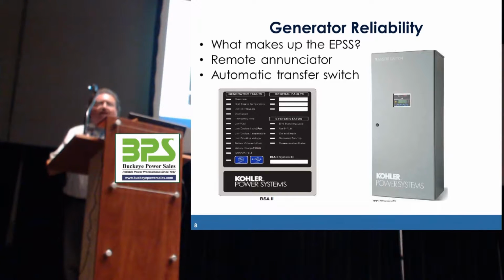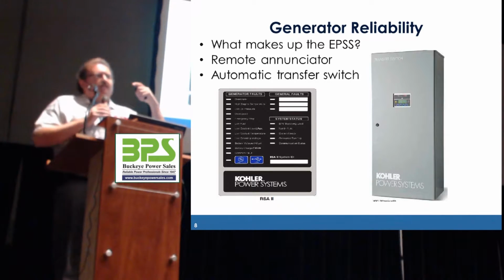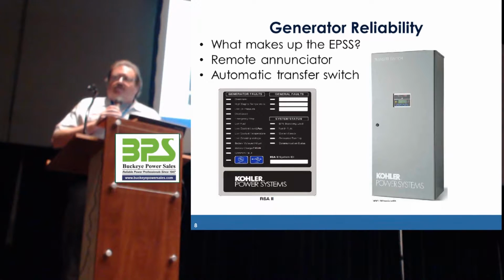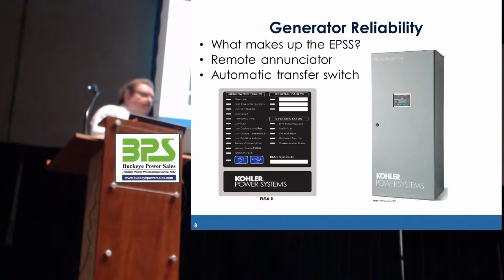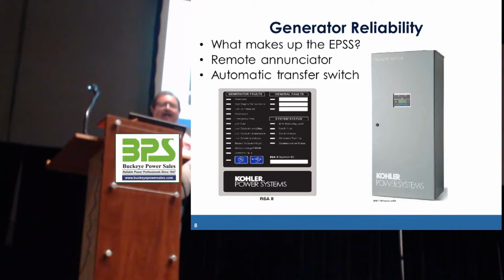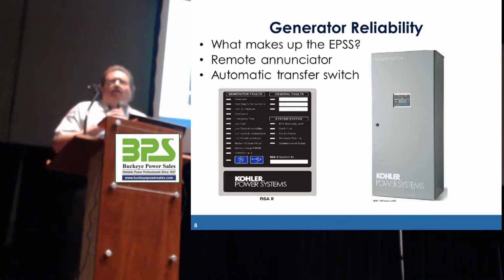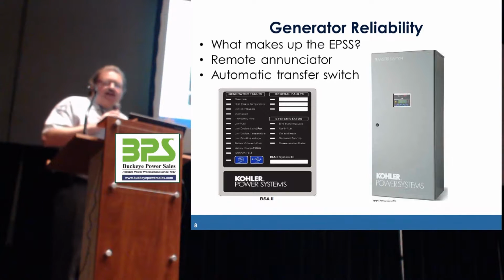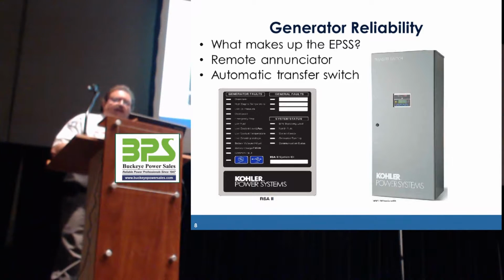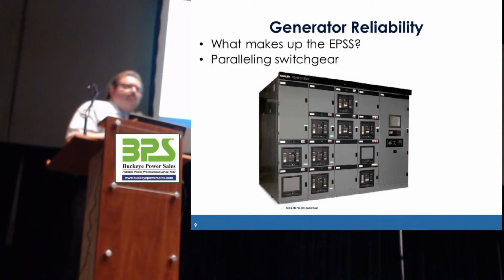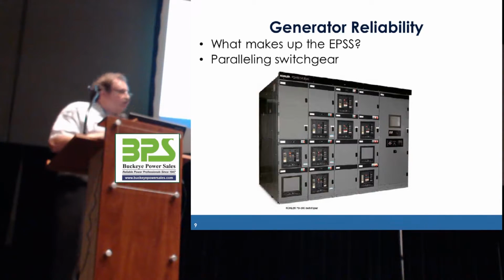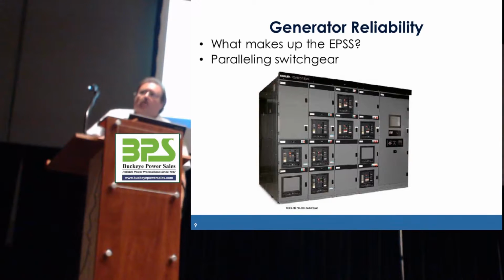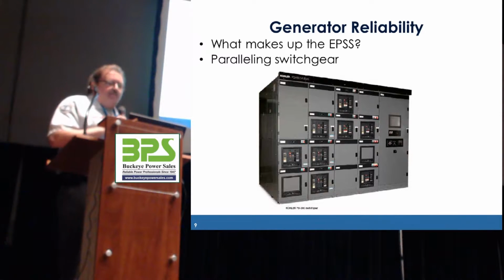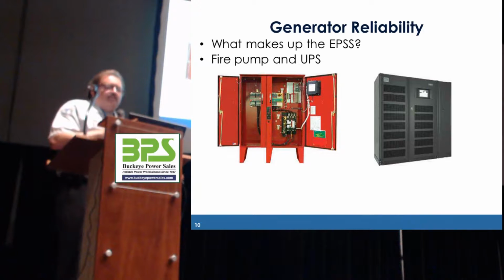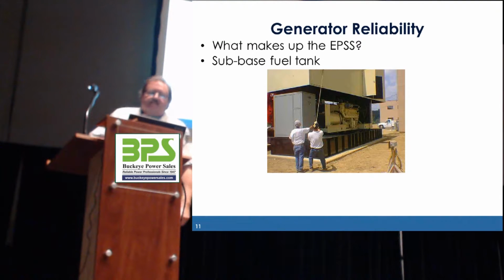These are just mimic panels that take the controls from the generator, the alarms, and put them in some place where they are monitored. Because if the generator's outside in a housing, out in the back of the facility, you're not going to hear the alarm when it has a low fuel alarm. So we have the remote annunciators that we have to look at to let you know when there's an issue. If you have more than one generator, you have potentially the paralleling switchgear. Like we said, fire pump controls, UPSs.